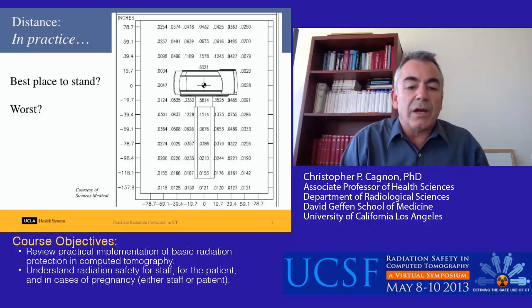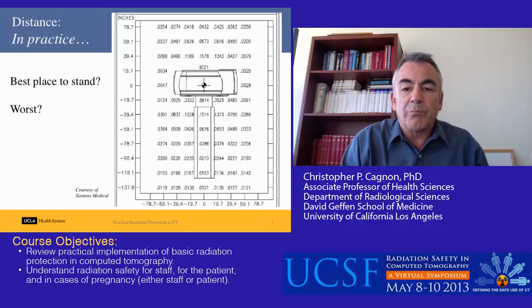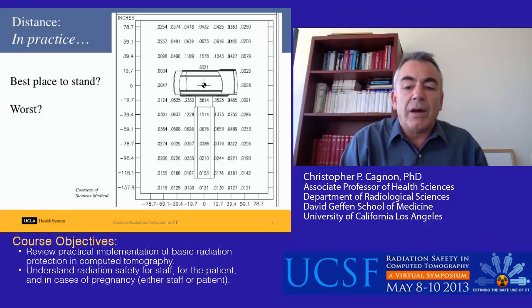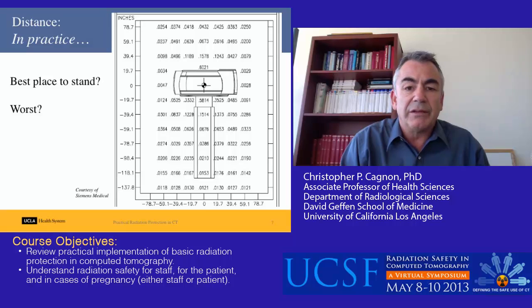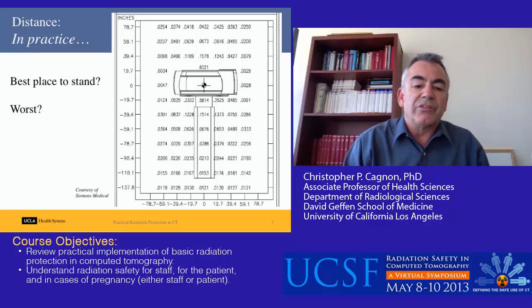Here's a radiation scatter and leakage profile plot courtesy of Siemens Medical Systems. This is what a physicist would use for site planning for shielding. These numbers represent actual doses for a certain technique with a phantom in the beam, creating scatter at different distances — all in the plane of the scanner. The question is: where is the best place to stand, and where is the worst place to stand?